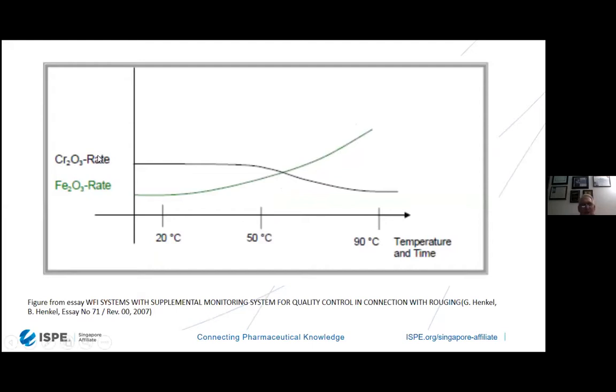This particular graph shows the development of chromium oxide, which is the oxide known as a passivation layer. That passivation layer is only 2.5 nanometers thick. It's a very, very, very small thin layer. It's not a firewall. And it decreases as the temperature increases. And notice that the ferric oxide rate, this showing hematite, increases sporadically from 20 degrees C and gets exponentially higher after 50 degrees C into almost 90 degrees C. So both the ferric oxide and the combination with the hydroxyls production is why the rouge is so prevalent in hot water systems. You don't want rouge in your system? Very simple. Don't use 316L stainless steel. Don't run them hot. Some of the best systems in the United States and in Europe run at 4 degrees Celsius and are completely oxygenated with ozone and are very, very, very pristine.